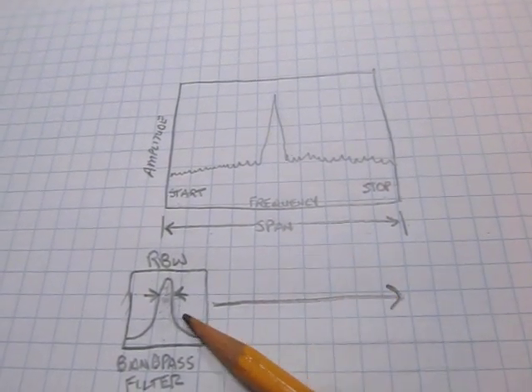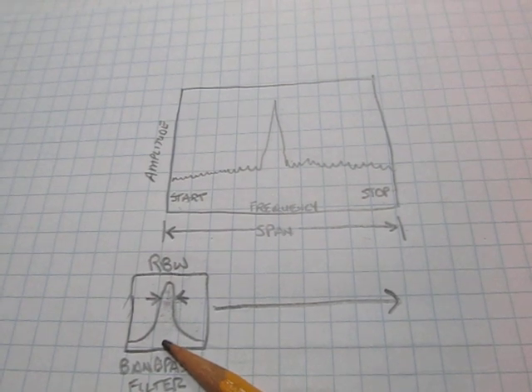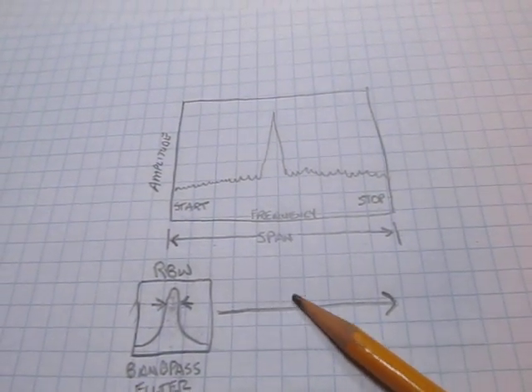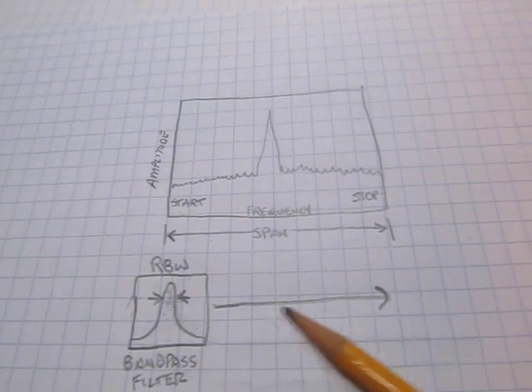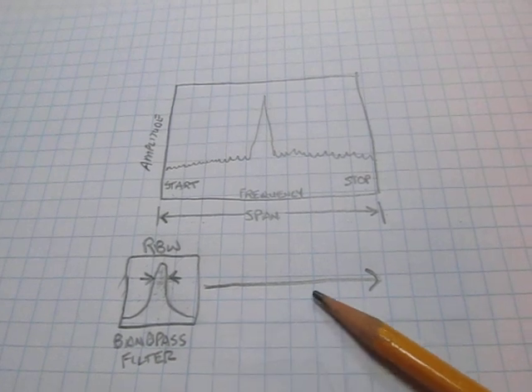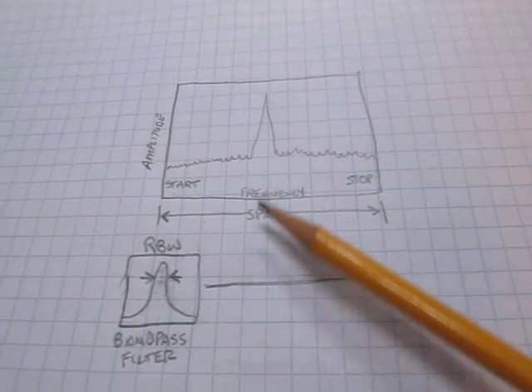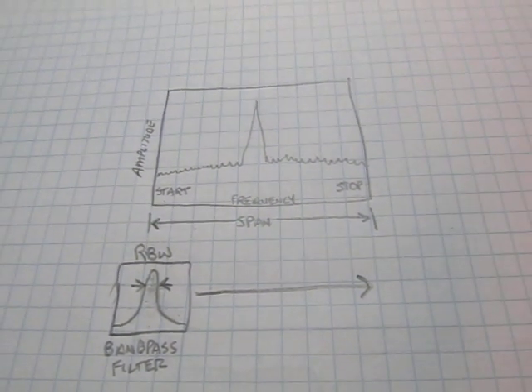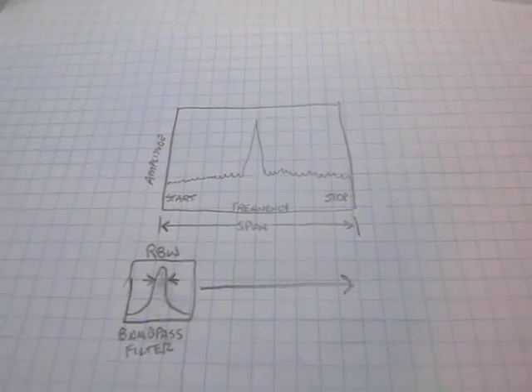Zero-span is quite simply parking that filter at a given frequency and then detecting the amount of power that exists in that filter over time. So it's kind of a time domain view of the amplitude variations of a given signal in that filter. So let's go take a look at what that looks like and how I set it up.